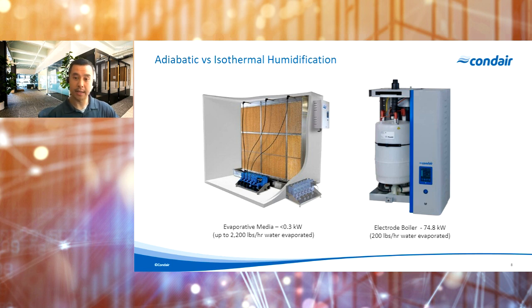kilowatts. Now, the other thing to consider here is with adiabatic or cold water systems is that the potential capacity or the evaporation rate really depends on the entering air conditions and the air volume. So if we were to look at one of our evaporative systems, for example, you could potentially output 2,200 pounds an hour while still consuming less than 0.3 kilowatts of electricity, since we're still using the same number of pumps and we're still pumping water to the top of the media. Now, as a comparison, if we were able to evaporate 2,200 pounds an hour and the air was able to absorb that, we could potentially cool that air or provide about 700 kilowatts of cooling capacity in addition to that moisture content increase. So you can see that for large evaporation rates for either humidity or cooling, adiabatic systems do make a lot of sense efficiency-wise.